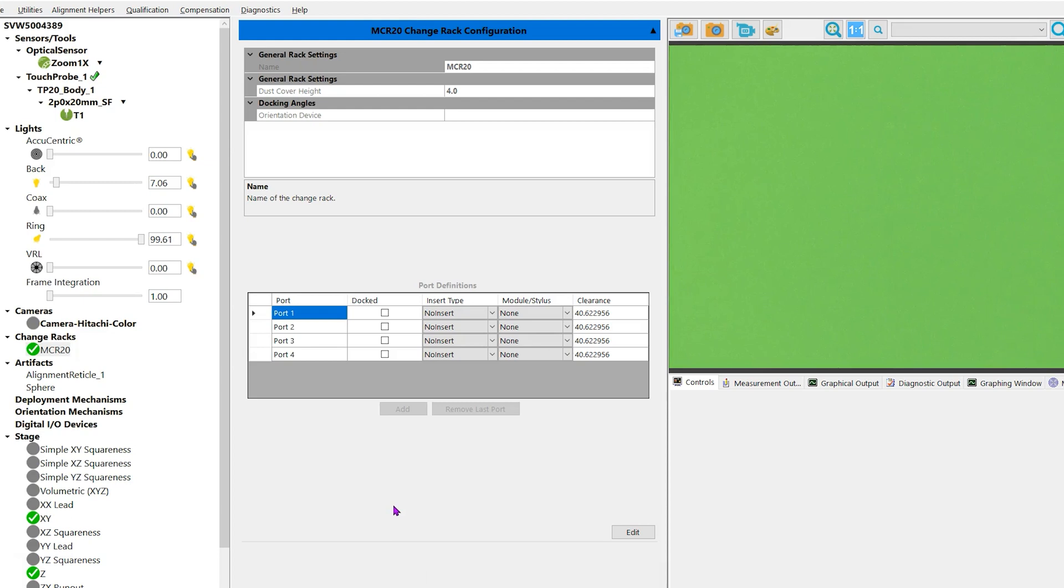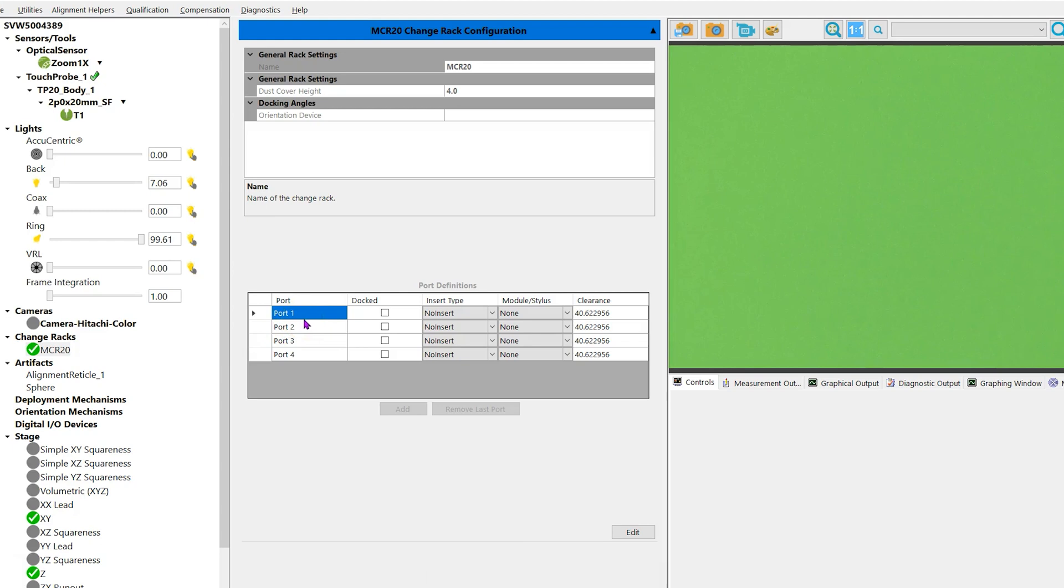In this example we're going to assign a probe called 2P0 by 20 millimeter SF to port 1. Make sure the tool rack is highlighted on the screen. Click edit and highlight port 1 with the left mouse button.